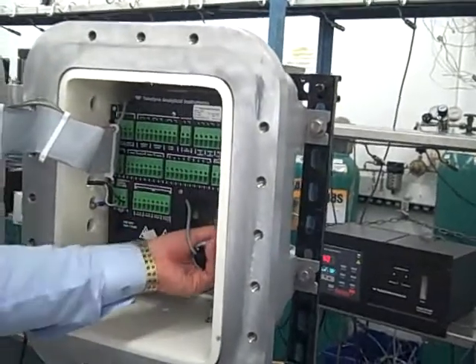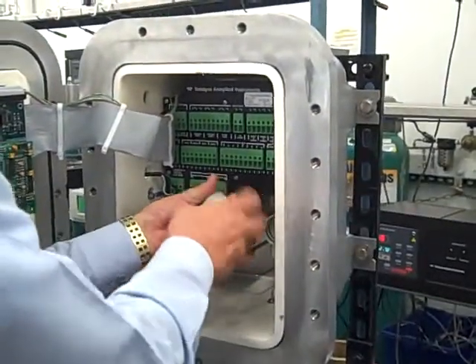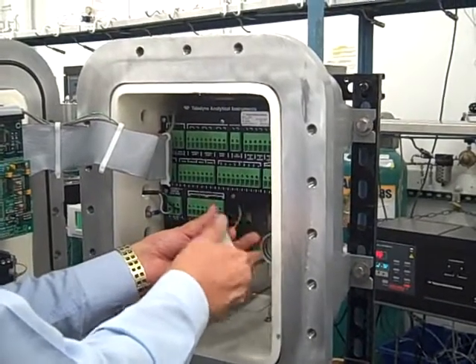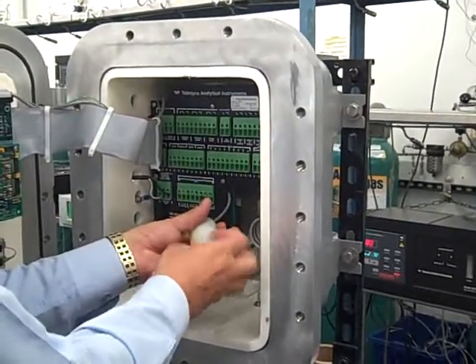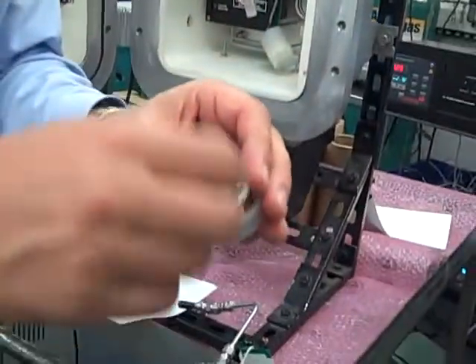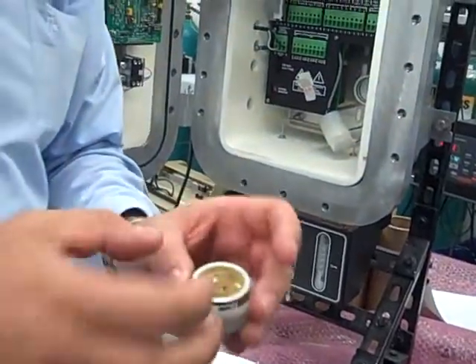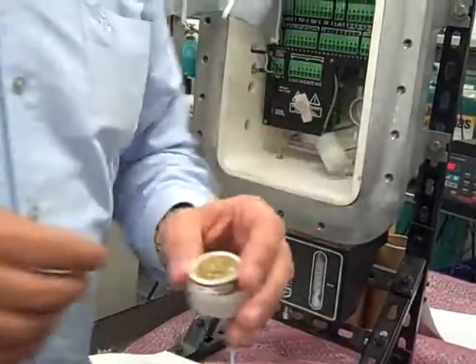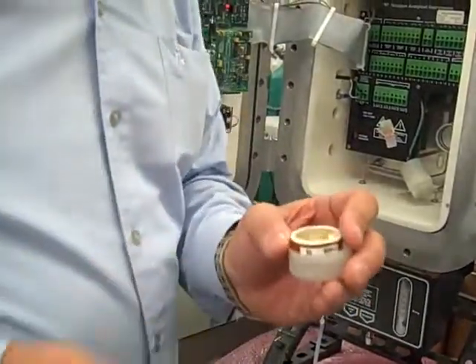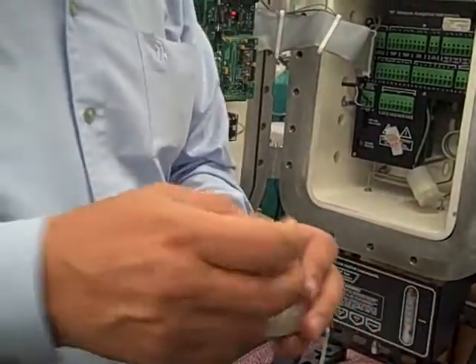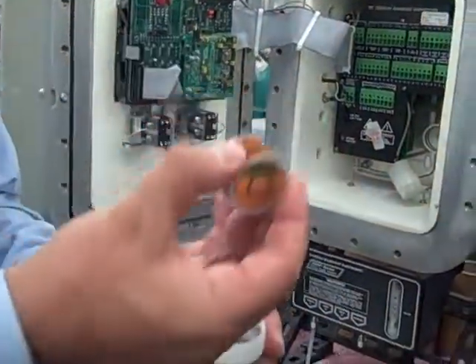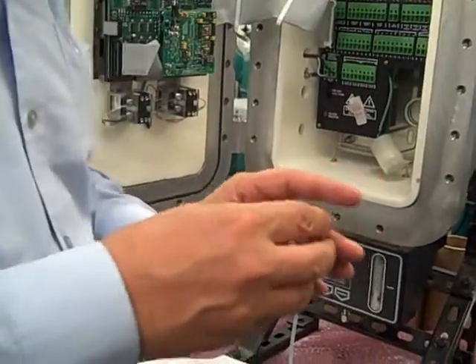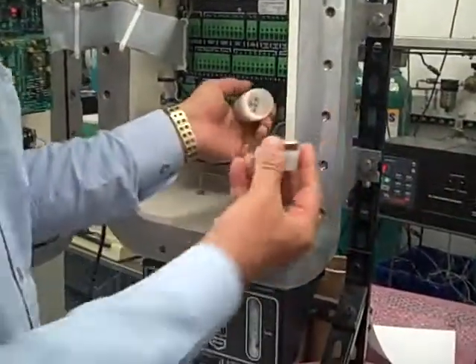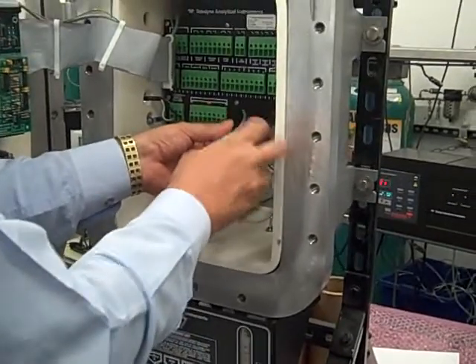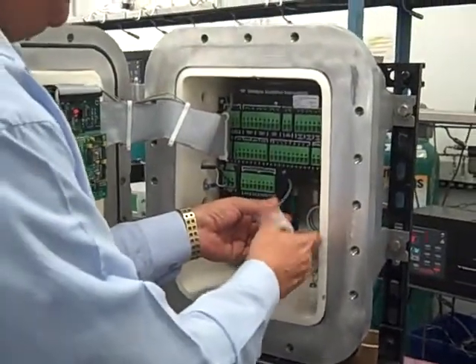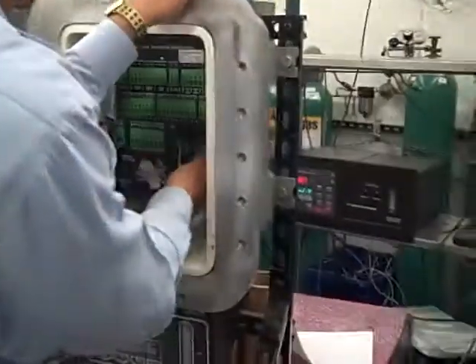Oh yeah, good point. My colleague who's helping me film reminded me of a very critical point, which is, when you get these sensors out of the bag, there will be a small button here. That's designed to short the output of the sensor while it's being transported. Before you put the sensor in the unit, remove that shorting clip. Get a small pliers or pull it off with your finger or whatever. It comes off fairly simply. Do not put the sensor into the unit with the shorting clip on there. You'll damage the sensor and possibly the unit. Okay, so thank you for reminding me of that. We put this in and again, screw it in, install it, and there you go.